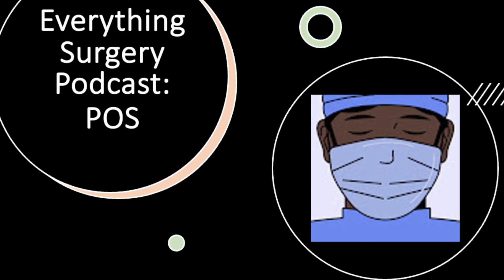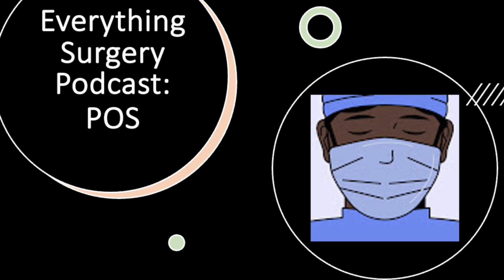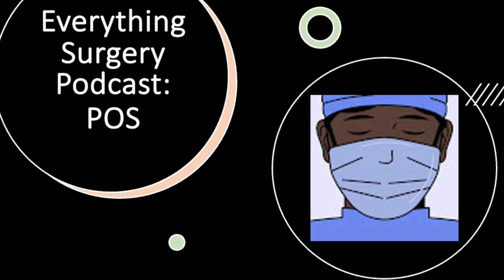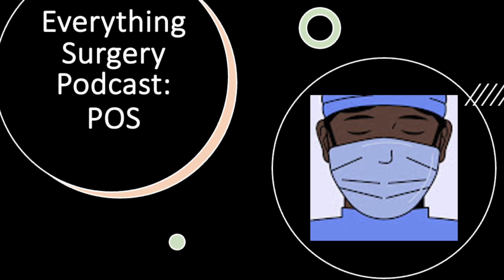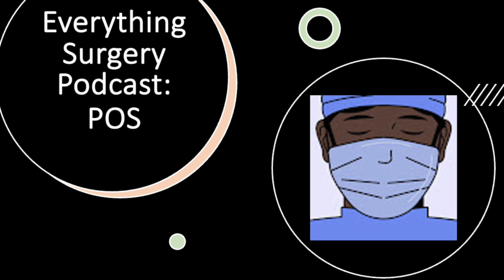It is crucial to distinguish between three related but distinct processes: cleaning, disinfection, and sterilization. Cleaning is the physical removal of organic material, like blood and tissue, using water, detergents, and mechanical action. This is always the first and most vital step, as leftover debris can shield microorganisms from further treatment. Disinfection takes it a step further, reducing harmful microorganisms to levels considered safe, though it does not eliminate all forms, especially the most resistant spores. Sterilization, however, is the complete destruction of all microbial life, and for any instrument entering sterile tissue or the bloodstream, this is absolutely non-negotiable.